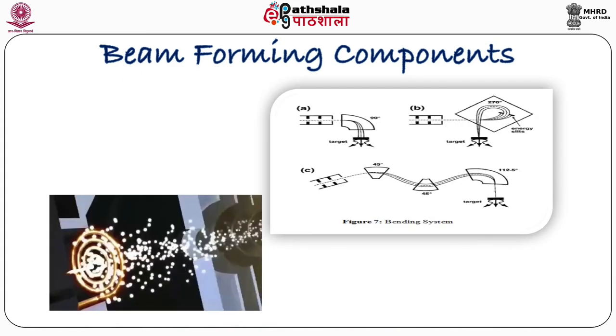In the figure, we can see the electron source filament from where electrons are coming out by thermionic emission. On the right hand side of the figure, we can see electrons are accelerated, moving along the waveguide, and finally with the help of a bending magnet, these electron beams are bent towards the target. When we want photons, we use the target — electrons strike the target and produce photons. When we want pure high energy electrons, this target is removed from the path and the direct electron beam is used.